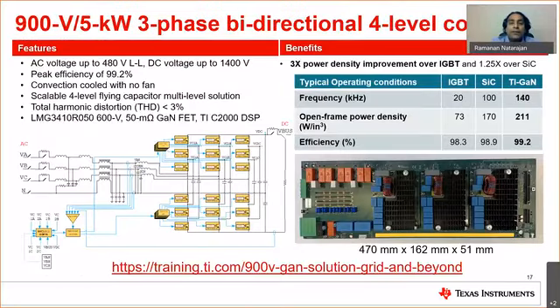Here is an example of a 4-level flying capacitor power converter, which is processing 5 kilowatts of power between a 900 volt bus and a 3-phase AC input. Here you can see the comparison between different technologies, including silicon IGBTs, typically operating at very low switching frequencies. And with gallium nitride, we are able to get the frequencies much higher than both IGBT and silicon carbide, resulting in higher power densities, over 3 times our power density, and still higher efficiency compared to the other devices operating at lower frequencies.